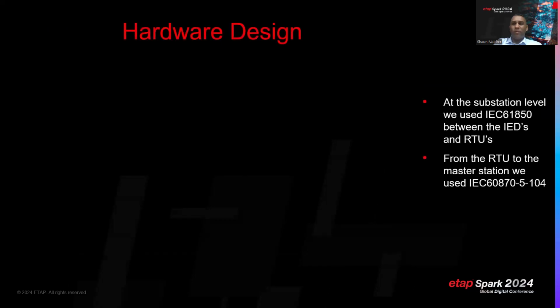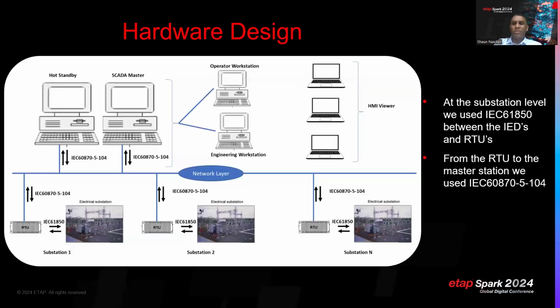At the substation level, we used IEC 61850 between the IEDs and RTUs for the newer equipment. And from the RTU to the master station, we used IEC 60870-5-104. And the architecture that we see on our screen right now is our existing architecture where we have our hot standby, our SCADA master, our operator and engineering workstations, as well as our HMI viewers. And at the substation level, we have our RTUs communicating with our substation equipment using IEC 61850.